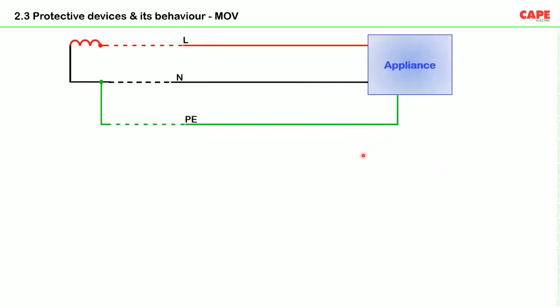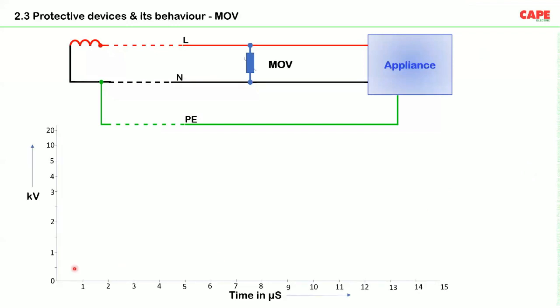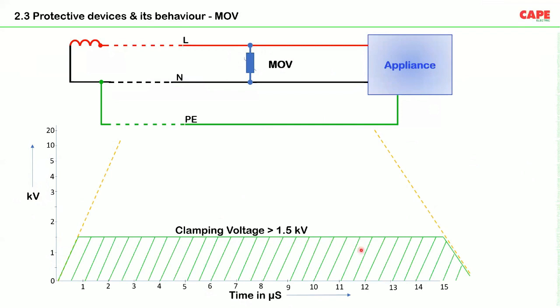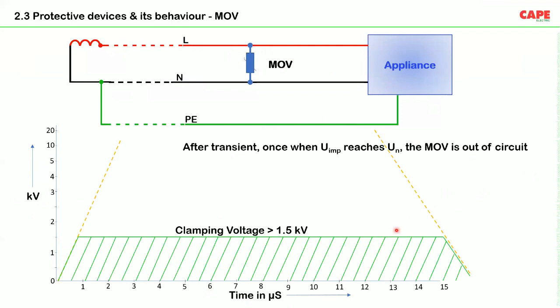Now, how do both these devices, the voltage clamping type device and the voltage switching type device, operate? Imagine you have the line, neutral, and PE. We are using an MOV type device, a metal oxide varistor type device. How this device operates is very interesting to understand. You have the voltage, in kV, and you have the time. You have the transient over voltage, shown as the dotted line here. These devices are called voltage clamping type devices, meaning they clamp the voltage to a level, let's say, for example, 1.5 kV. After the transient, once the impulse voltage reaches the nominal voltage of 230 volt, the MOV is out of circuit.